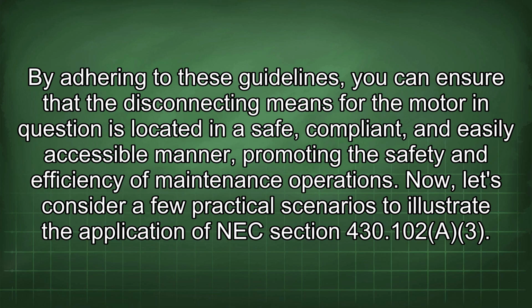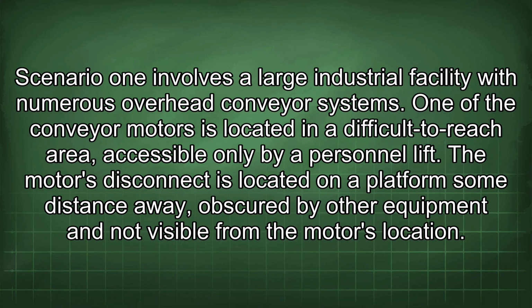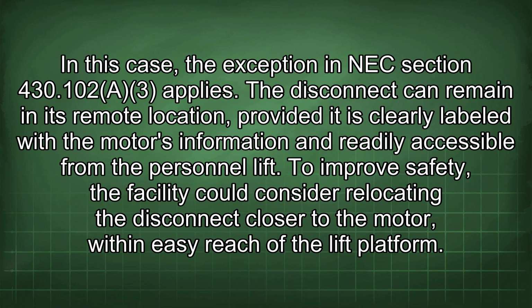Now, let's consider a few practical scenarios to illustrate the application of NEC Section 430.102 A3. Scenario 1 involves a large industrial facility with numerous overhead conveyor systems. One of the conveyor motors is located in a difficult-to-reach area, accessible only by a personnel lift. The motor's disconnect is located on a platform some distance away, obscured by other equipment and not visible from the motor's location. In this case, the exception in NEC Section 430.102 A3 applies.